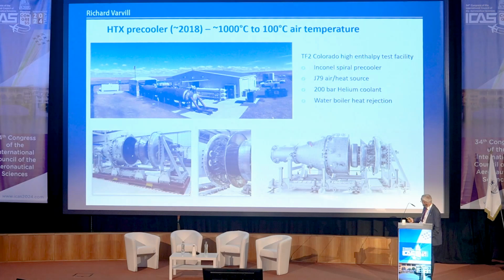This is an exploded version of the facility. The hot air was coming in here, then flowing radially out, and then radially back in through the pre-cooler, which you can just see there. The whole assembly has been split apart in this picture. So it was taking in 1,000 degrees C air here, cooling it, and then sending it back into the axial direction. In this case, we weren't using liquid nitrogen as the heat sink, we were using water, boiling water in fact, so it was cooling the air down to about 100 degrees C. But otherwise very similar, using helium at 200 bar as the heat transfer medium in the pre-cooler.